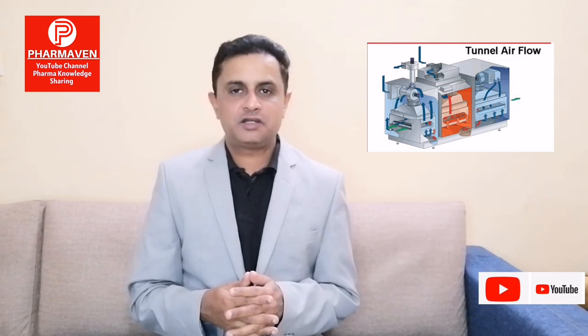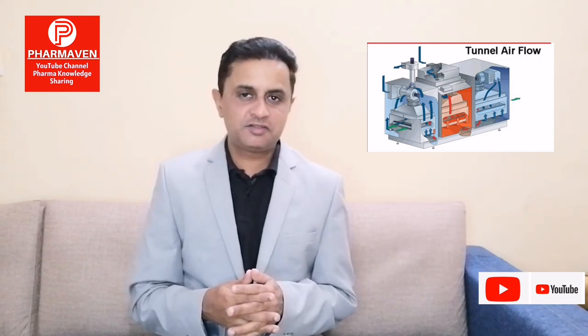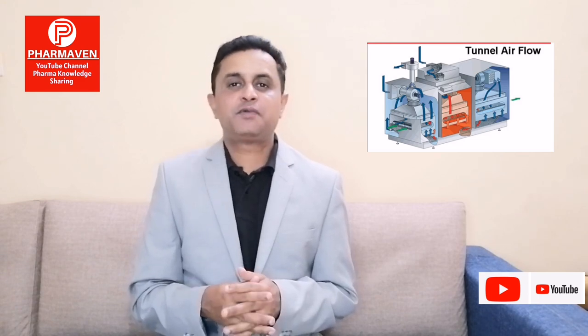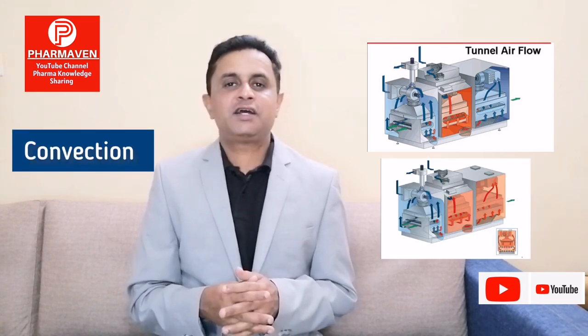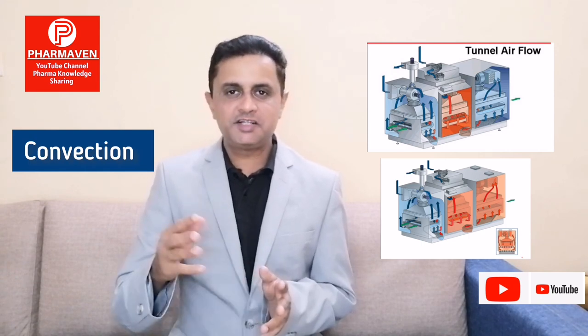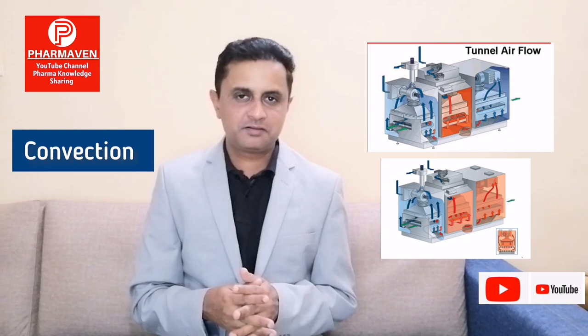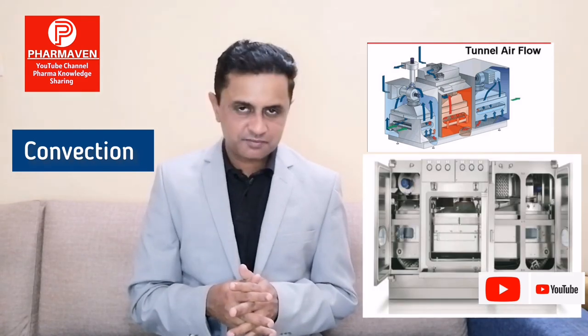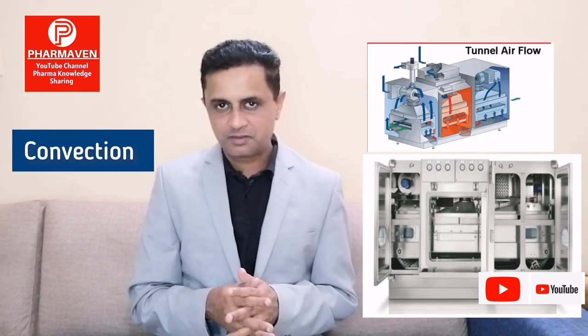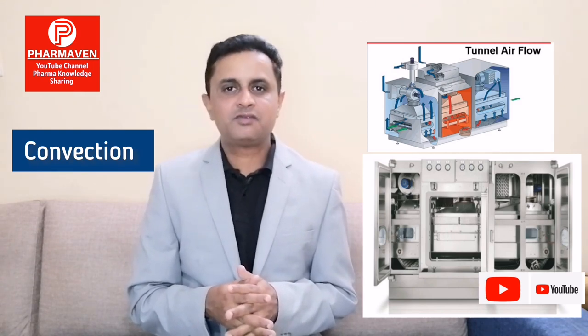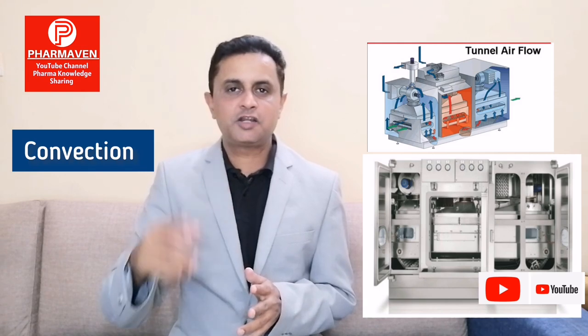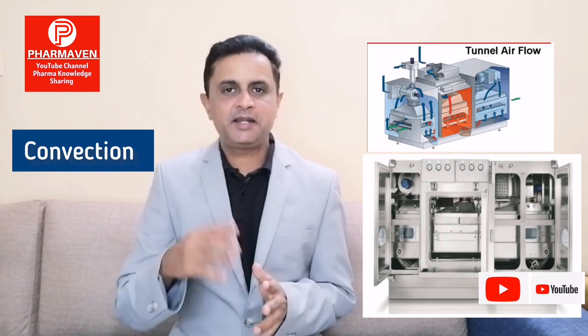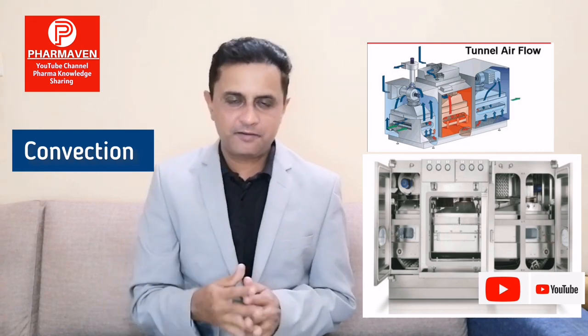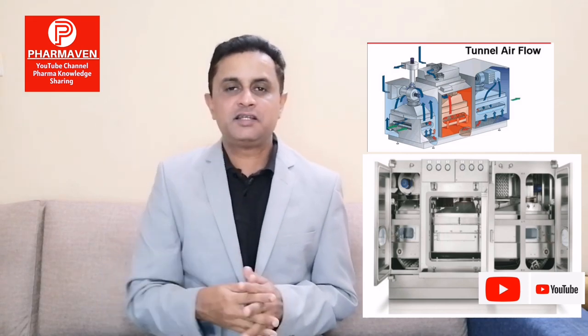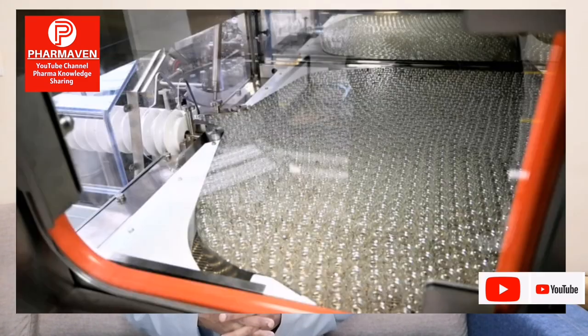So how does hot air work, how does heat transfer in hot air depyrogenation work? It is by the principle called convection. There are convection currents by which heat is transferred. So how does it happen inside the tunnel? The tunnel is fitted with heater banks and a blower to circulate the air. The air is circulated through the heater bank. The heater bank transfers the heat to the air, and that heated air then transfers the heat to the glass containers, the glass vials, which are inside the tunnel conveyor.